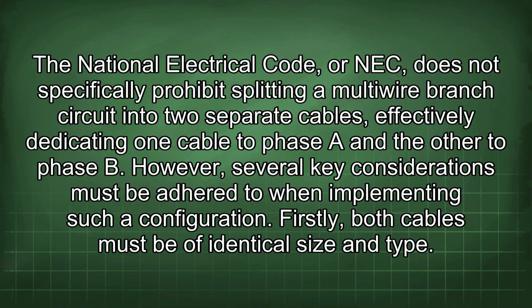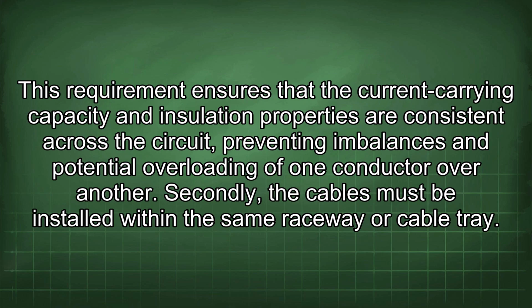Firstly, both cables must be of identical size and type. This requirement ensures that the current carrying capacity and insulation properties are consistent across the circuit, preventing imbalances and potential overloading of one conductor over another.